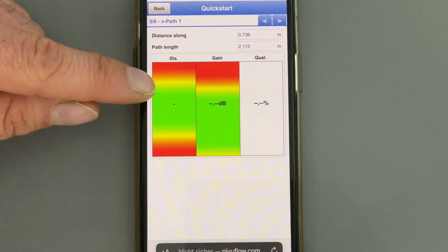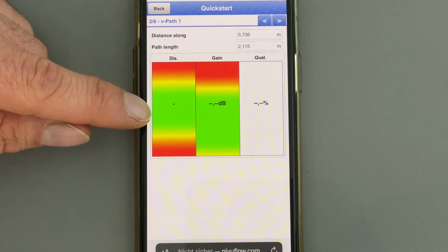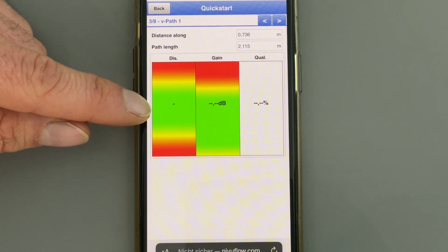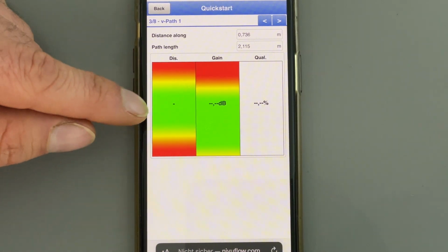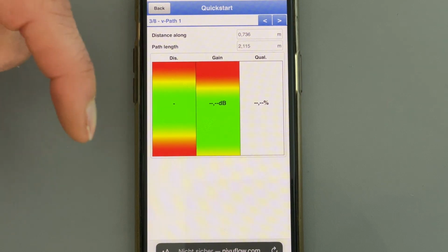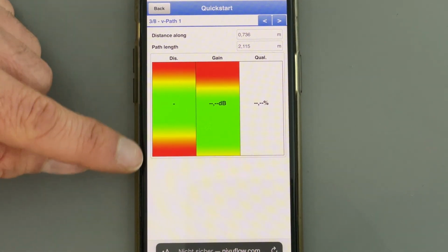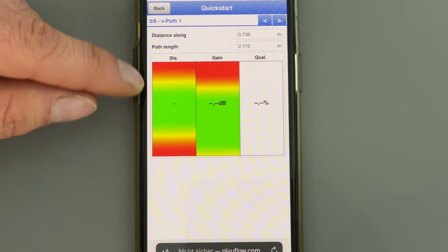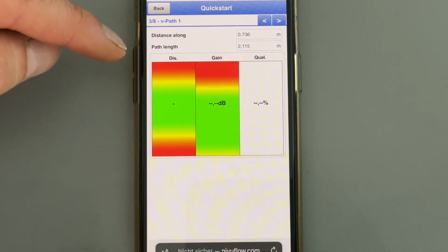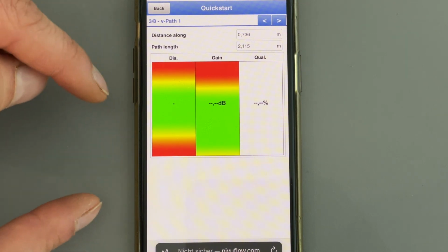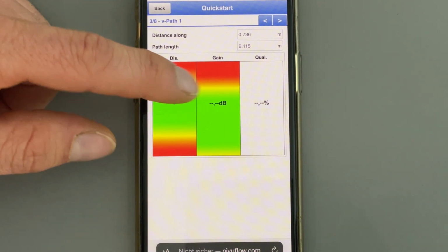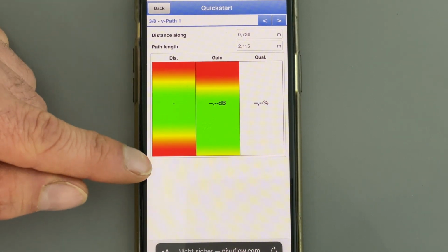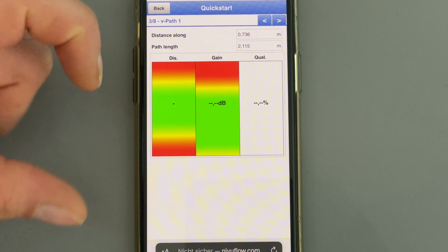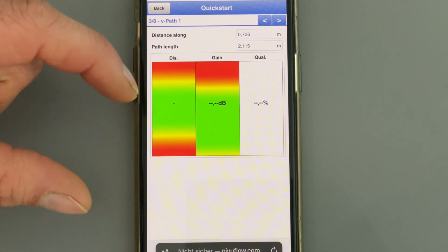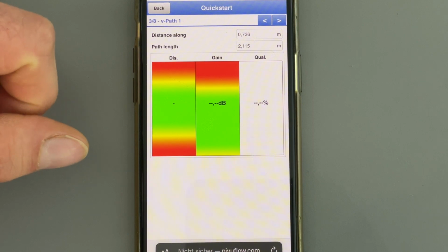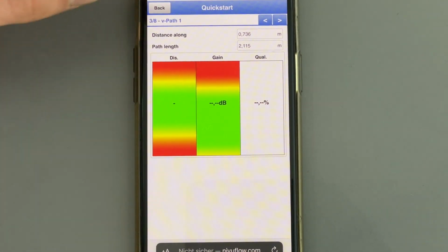Here in the color-coded display, it shows you if the sensors are aligned well enough. So if it's always in the green area, it's good. If it's in yellow or red, the sensor needs readjustment. Here in the first column for the distance, if it's in the upper area, they are too far apart. So you need to bring them a bit closer together and see if the dash changes to the green section. If it's too much in the lower area, that means they are too close to each other, so they need to be separated a bit, and then see that the dash moves towards the green area.